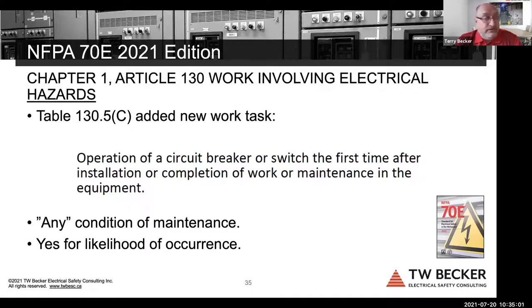Power circuit breakers are removed every 3 to 5 years, and significant testing is completed and other maintenance on that circuit breaker. Rack it back in, the first time you close it or open it, this would then imply arc flash PPE needs to be worn. Now, I'm advocating that once we get it back to normal operating condition or normal equipment condition to operate, we do not need arc flash PPE.